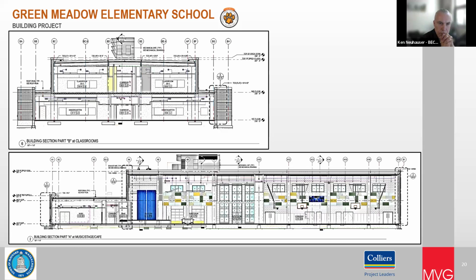This is getting me closer to understanding how it's working. So the discharge air temperature from the rooftop units and DOAS units can be independent of the set point in the classrooms, based on need. If our set point limit can't go below 72, we can still supply air at 68 degrees, and other temperatures can reheat that air, while one classroom could let it come in cooler to help cool down a bit.